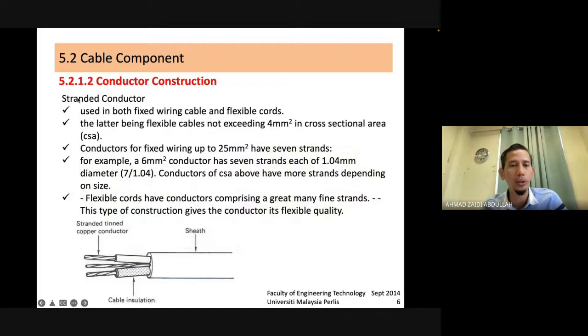Conductor construction. Let's say stranded conductor. We have stranded, so how many are there inside? It is used in both fixed wiring and flexible cord, the latter being flexible, not exceeding 4 mm in cross section, so it cannot be more than 4. Conductors for fixed wiring up to 25 mm have 7 strand. This is in the standard. Conductors for fixed wiring from 1.5 mm up to 25 mm must be 7 strand.